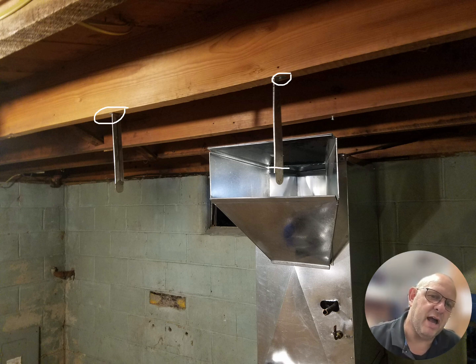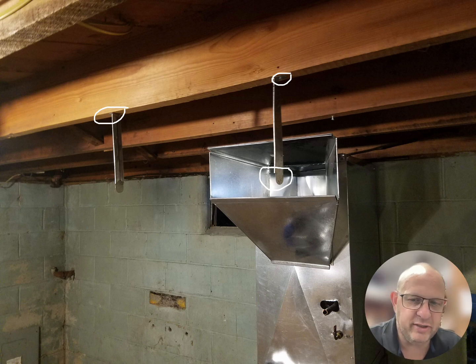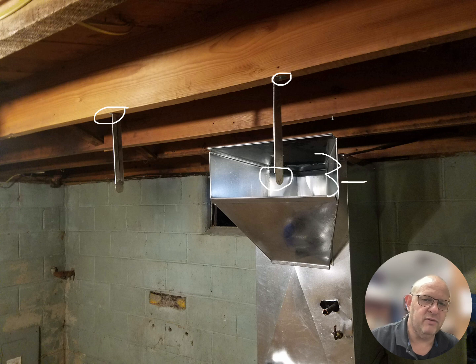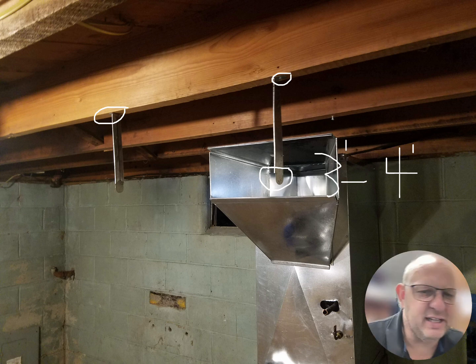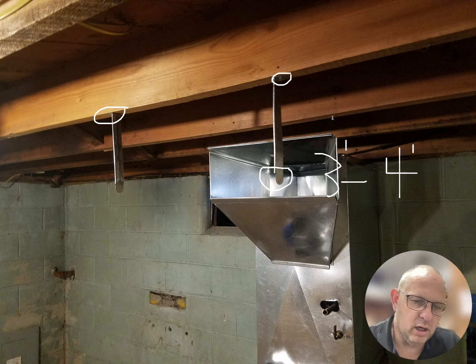The tabs that are on the bottom of the drive cleat, I will take that and put that on the bottom side of the ductwork so it holds it. And then I'll put another screw in that guy to hold the ductwork in place as we are hanging it along the joists every 3 to 4 feet for our rectangular ductwork. We're going to put hangers up and get them hooked up in there. I always like to see 2 hangers on a 5-foot ductwork. It helps with the weight distribution on the hangers, but also gives a good foundation to running that ductwork along it.